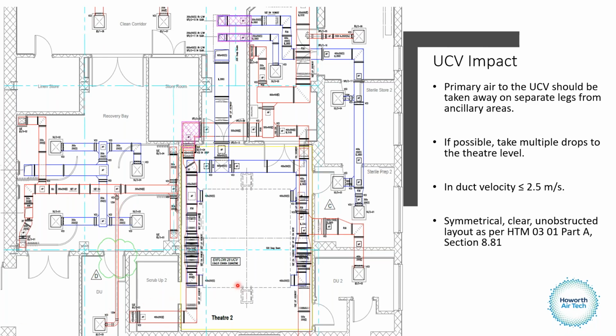An important thing to consider when you've got a UCV is to take the supply duct as far away from the other rooms as possible, the ancillary rooms. So the canopy sits here in the centre. This is an example. In-duct velocity should be no greater than 2.5 metres a second, and the primary air should be balanced to this system in a fashion that's easy to do. So you've got VCDs within the duct, and you can see that the ancillary rooms are in other areas of the floor. This was a project that Howorth did a couple of years ago.